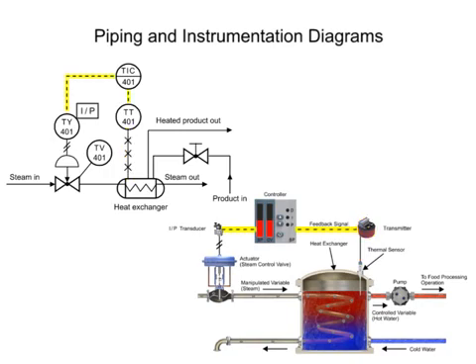A dashed line between components indicates an electrical signal. The controller and indicator is the instrument where the transmitter sends an electrical signal and is shown in the functional identifier at the second and third letters, I and C.